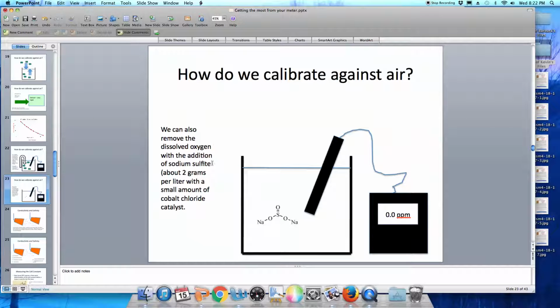Sodium sulfite used to be added to water supplies for steam boilers to remove oxygen because the presence of oxygen in the water supply might cause the steam boilers to rust. This is a good way to test your meter to make sure that it is working at low concentrations of oxygen, and this procedure is also required by the New Jersey Department of Environmental Protection.